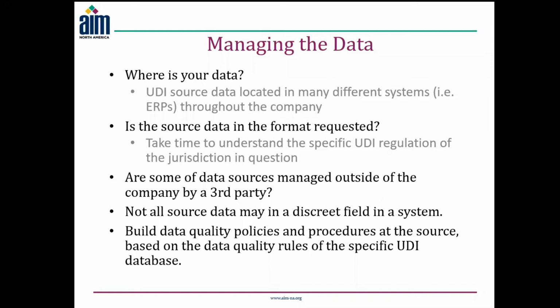And I'm going to close with this last point. I think this is probably one of the most important things we've heard from manufacturers about making sure, as I like to say, your data is fit for purpose, fit for the intended purpose. Understand the data requirements of the database in which you're trying to store that data, that UDI database. Understand if there are validation rules or prerequisite requirements, and then build those into your internal company policies at the point where you're creating the data. So have the policy and procedures that reflect where the data is going to end up, because if you do that, there's a higher probability that it'll be fit for purpose.